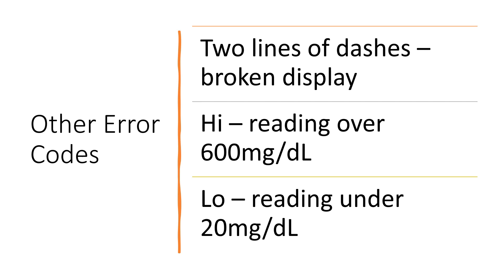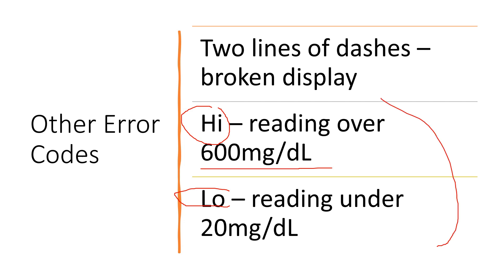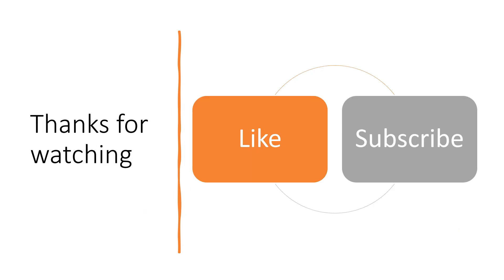Other codes: two lines of dashes indicate the display is broken and it's time to replace the meter. 'High' can mean that your blood sugar reading is over 600 milligrams per deciliter. 'Low' could mean that your reading is 20 milligrams per deciliter or lower. You'd want to retest in both situations, and if it continues to read high or low, seek medical attention. Thanks again for watching — I hope you found the information useful.